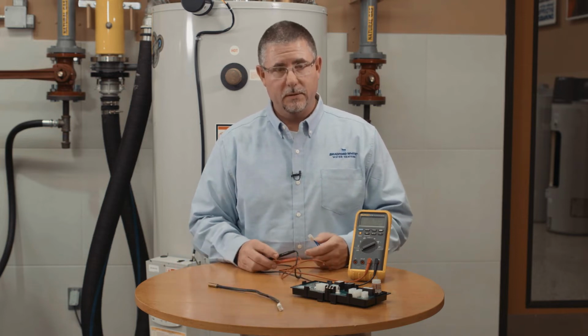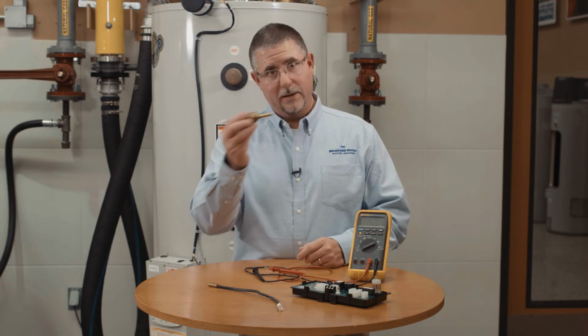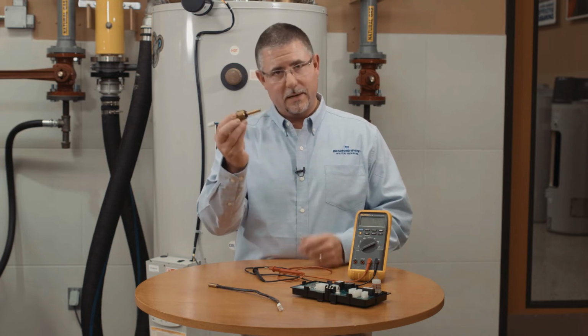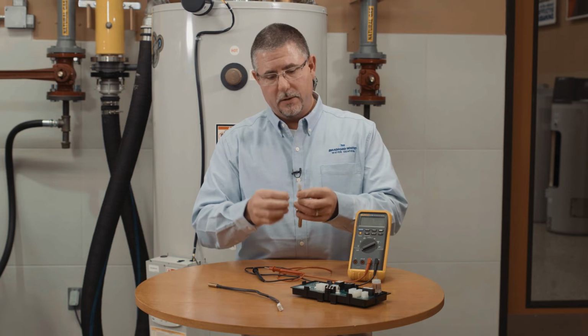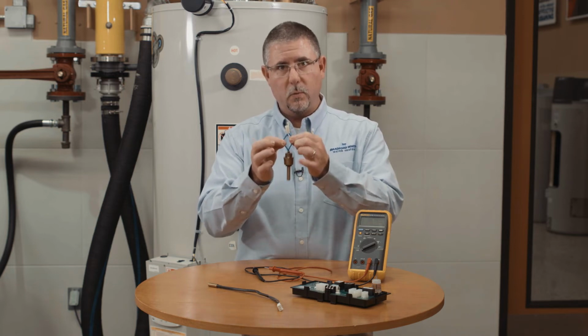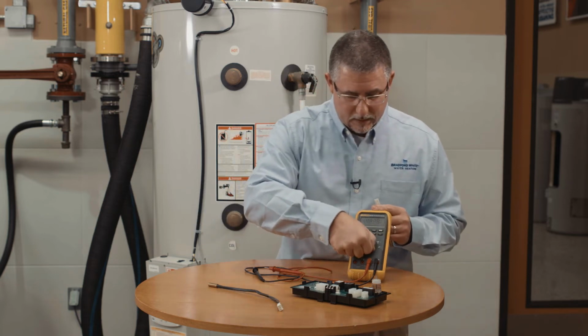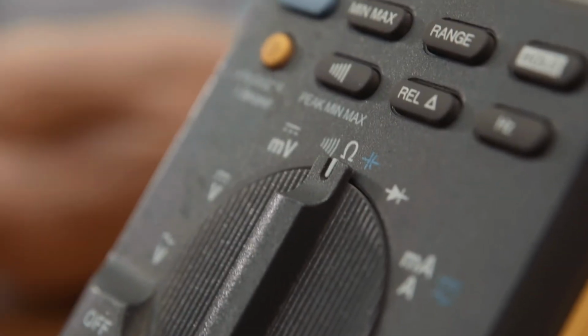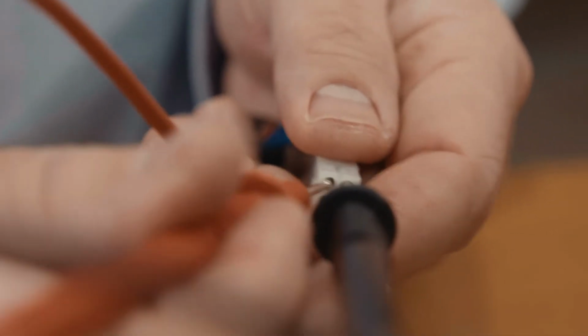Error codes 31, 32, and 65 are going to have us use our multimeter to actually measure resistance. Remember, the 2-wire sensor is embedded into the water, so we're going to measure resistance from one wire to the other. The resistance setting is, remember, the upside-down horseshoe symbol.